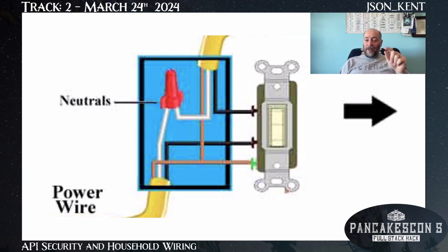Why? Well, you see how your light switch has a bunch of metal around it? Well, what happens if that hot line touches that metal and then you reach up to grab the switch? Well, you could potentially get electrocuted. So they ground everything out so that way it'll draw a ton of current and trip the breaker. The whole idea here is trip the breaker in order to make it safe.